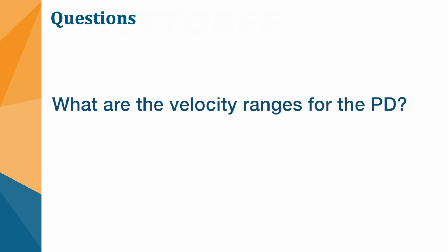For the AMPD, once you start getting below 300 feet per minute, your accuracy is going to get worse. We've got some accuracy data for that lower level up to about 2,000 feet per minute for the units we do have, so it's not going to be on, say, the first page.